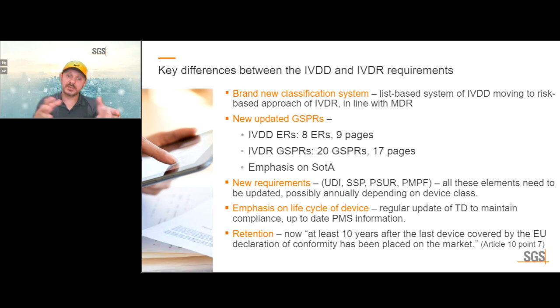There's a huge emphasis on state-of-the-art. Devices are no longer evaluated in a vacuum — they are assessed in the whole context, looking at all alternatives that could provide the same diagnostic result. Manufacturers also have to consider non-IVD tests, such as an in vivo test, when evaluating whether their device represents the state-of-the-art. If an in vivo test results in better specificity, accuracy, or repeatability, their IVD may not be considered state-of-the-art.